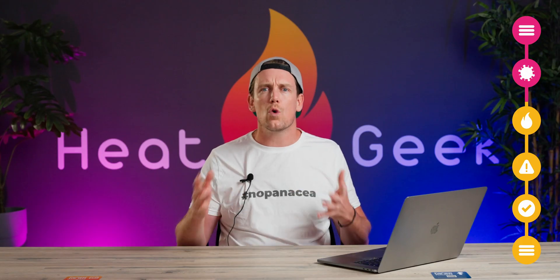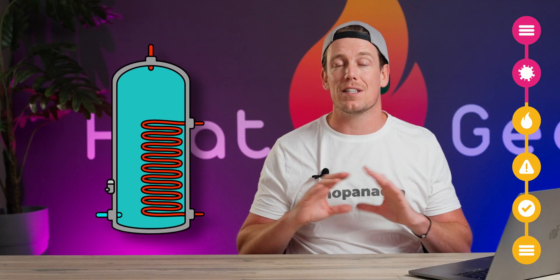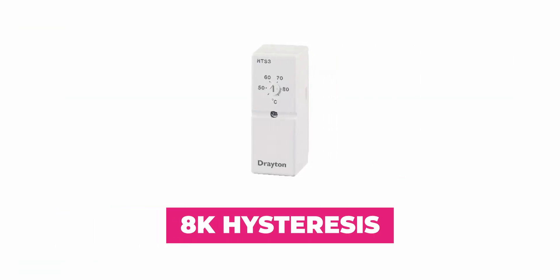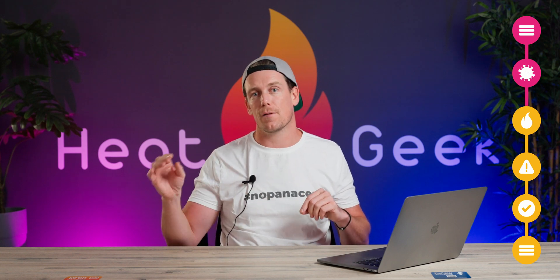So how accurate are your measured temperatures? Let's assume your hot water thermostat is calibrated. Because cylinder thermostats are located a third of the way up the cylinder, the temperature at the top will likely be a few degrees above your target stat temperature due to stratification. Below the thermostat will be between 10 degrees Celsius — the incoming cold water main temperature — and the stat set temperature. But for safety let's just assume it's all the same temperature. Cylinder stats also have a hysteresis — for example, this common thermostat has an 8K hysteresis or switching differential, so if set to 50 degrees Celsius it will call for heat when the hot water's down at 46 degrees and turn off when it's up at 54.